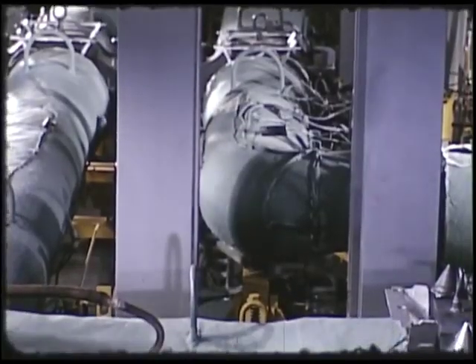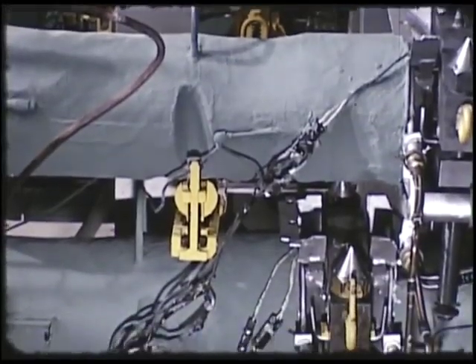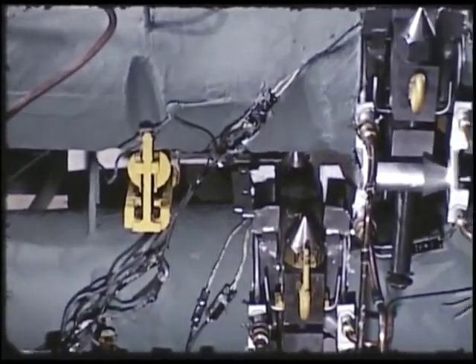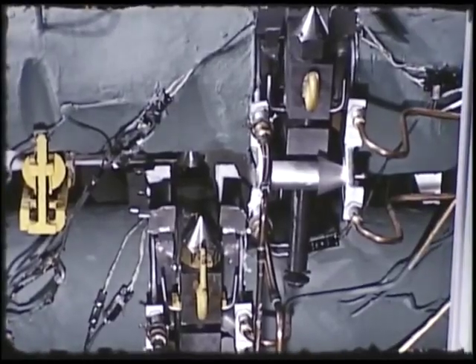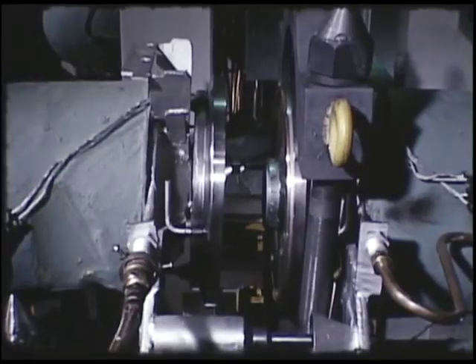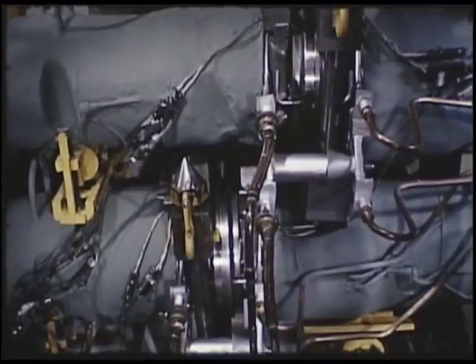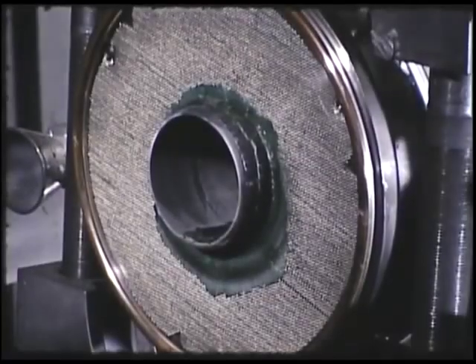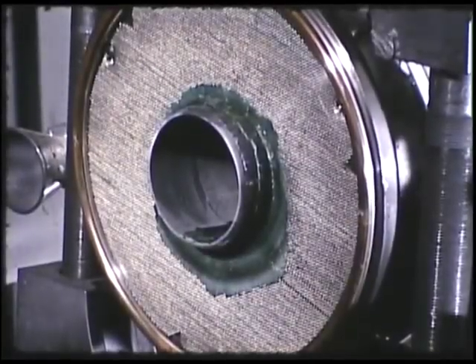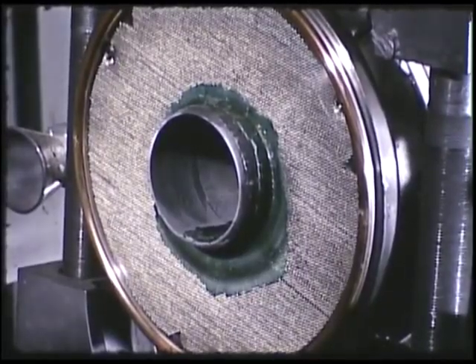To remove and replace a component, it must be possible to break and remake pipe connections to extremely leak-tight specifications. Considerable attention, therefore, was given to the design and development of a suitable mechanical joint which would lend itself to remote assembly. The freeze flange developed at the laboratory is used at 20 locations in this system. Such a joint takes advantage of fused salt properties to form a frozen seal of the process material between flange faces.